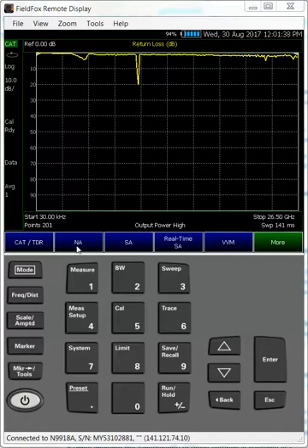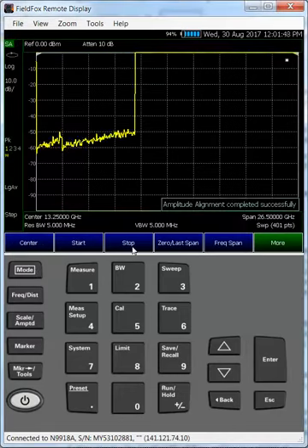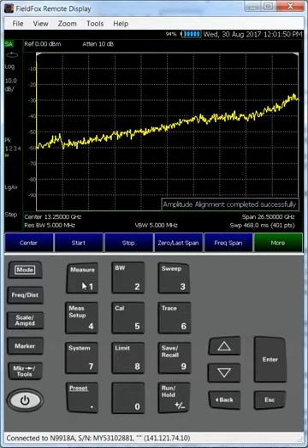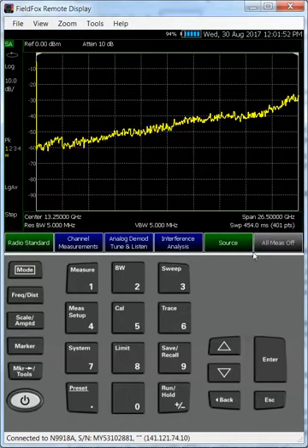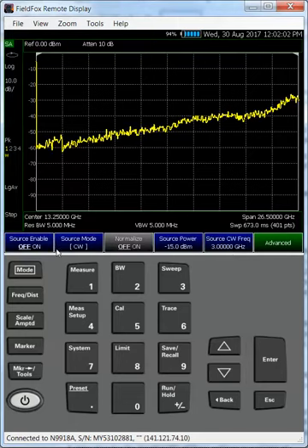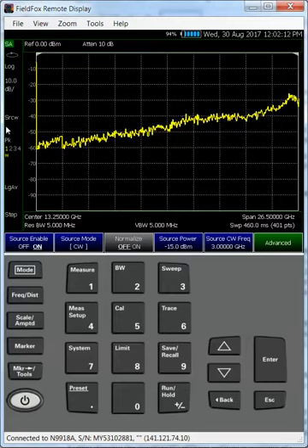In this video, we will look at FieldFox's tracking generator or source functionality. If you preset a FieldFox and you go into the spectrum analyzer mode, and then you press measure, there's a key called source. And if we press source, that's the tracking generator where you get to it. You come into the source menu, and here we can enable the source. And if you enable it, if you notice on the left here, you get the source annotation.